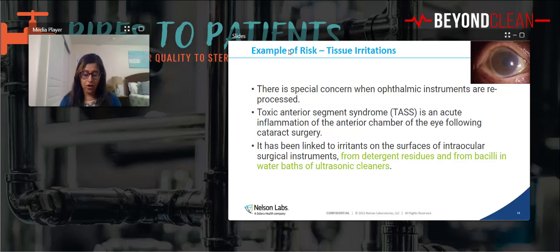And a lot of the time for ophthalmic devices, we do use water. It's because detergents, if you think about it, if you wash your face with soap and you get soap in your eye, that's a detergent. It stings. So you don't want to use detergents, and if you do, you want to use them at a very, very diluted level. But if you're diluting it with the wrong type of water, you just created this problem like we just talked about. So even if you're diluting the detergent to clean these instruments, you want to make sure that you're using the right type of water.